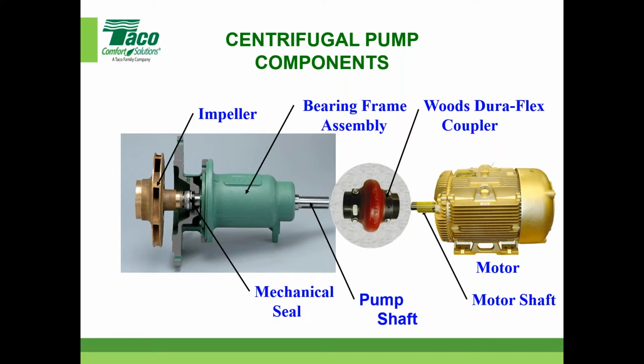So the seal is one of the components that you really need to watch. It's not good when it starts dripping. That's probably the part that wears the fastest on pumps. And again, it has to do with the system water and cleanliness. But nonetheless, that's probably one of the parts that does need to get replaced at some point in time. There's the pump shaft.